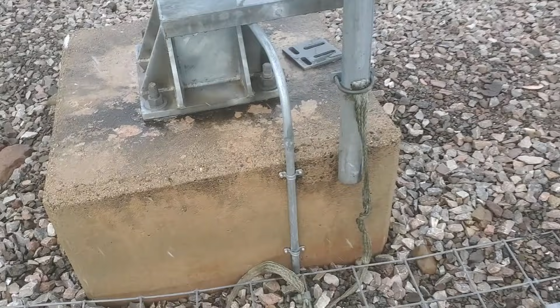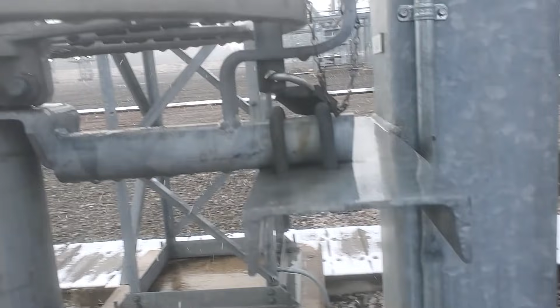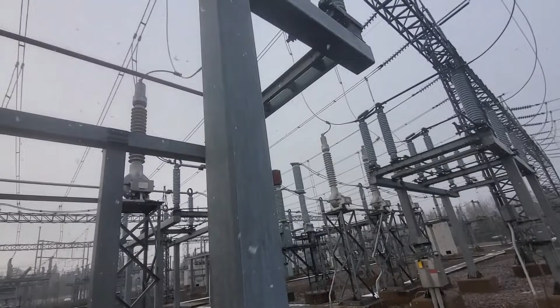Which brings me to the third and final step of what you should do whenever entering a substation or switch yard, and that's a general inspection of the equipment. What makes our system most dangerous is when it's compromised. Everything in this sub yard is bonded together, every bit, the steel building, the ground grid, the towers, any equipment, switch handles, everything is bonded together to be at equal potential. Just a general inspection of the area, making sure everything's safe.